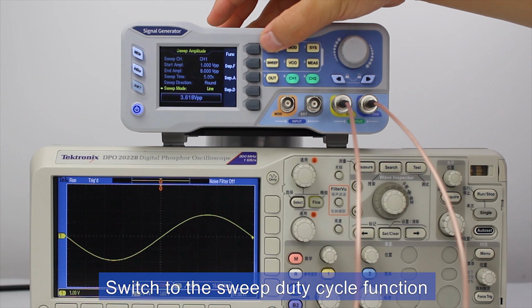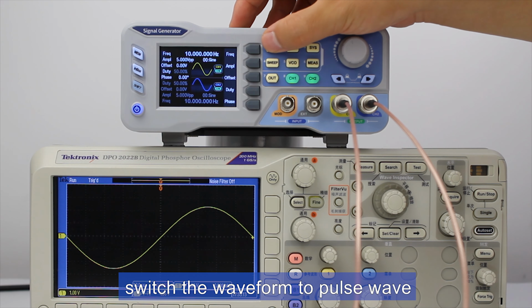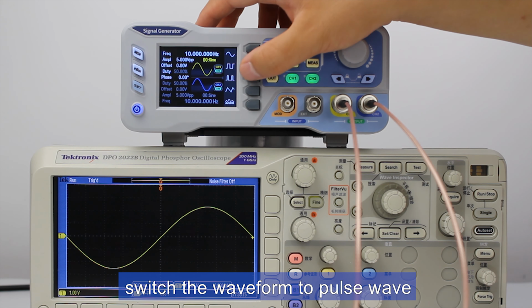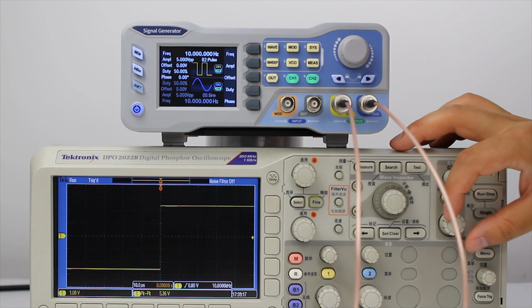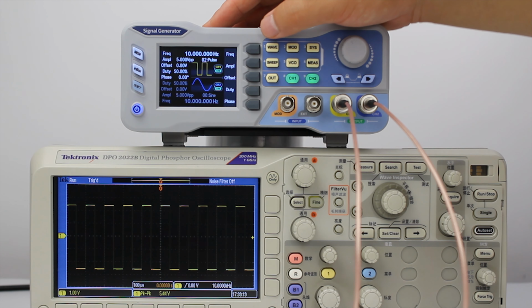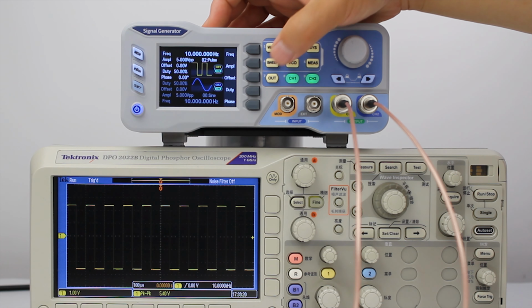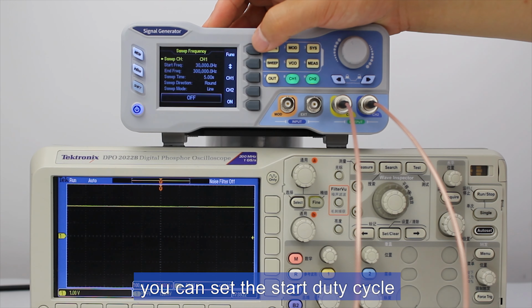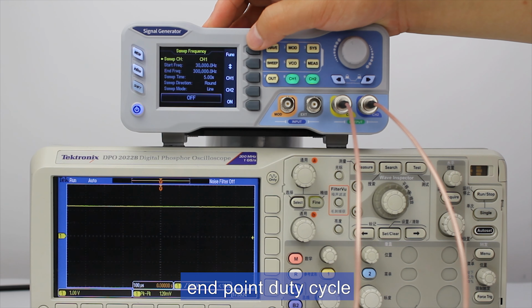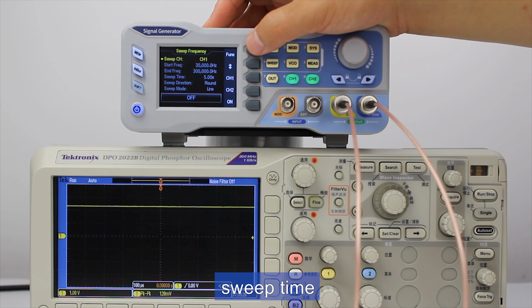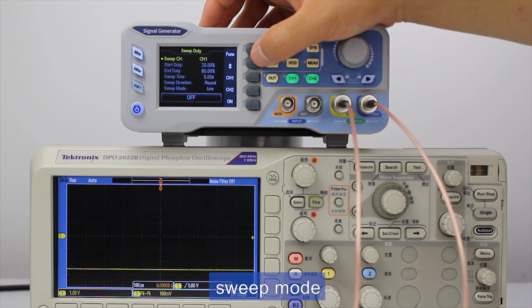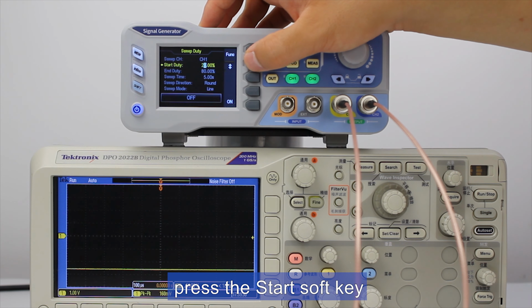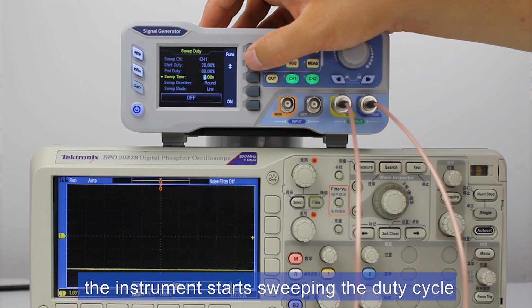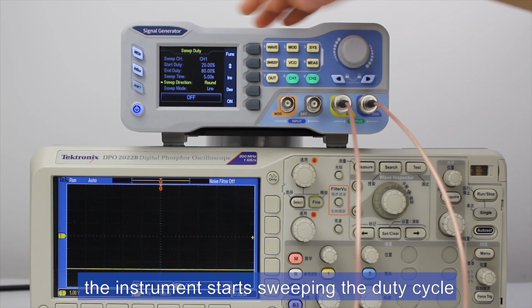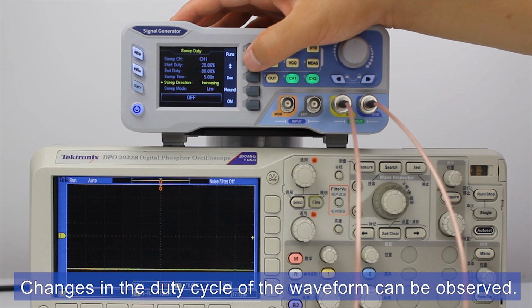Switch to the sweep duty cycle function. Switch the waveform to pulse wave. You can set the start duty cycle, endpoint duty cycle, sweep time, sweep direction, sweep mode. Press the start soft key. The instrument starts sweeping the duty cycle. Changes in the duty cycle of the waveform can be observed.